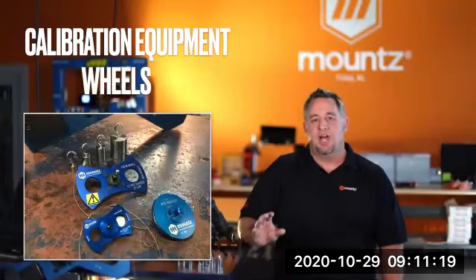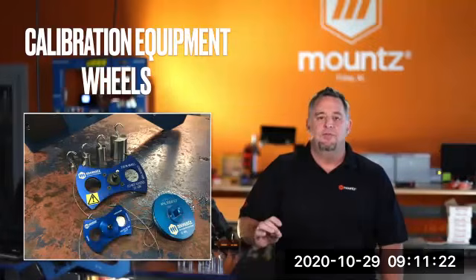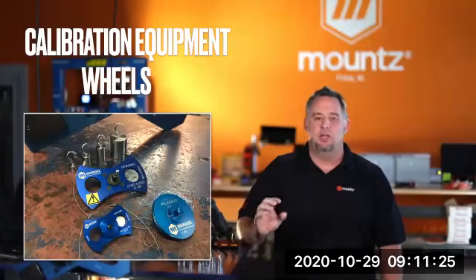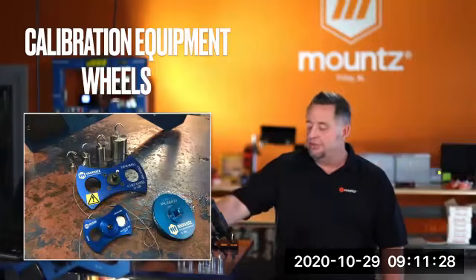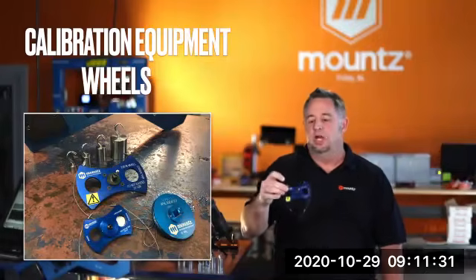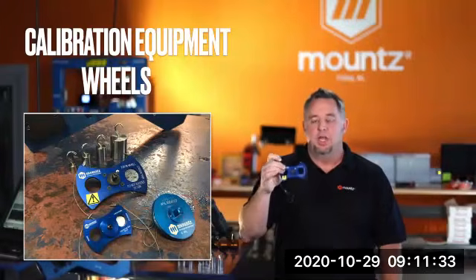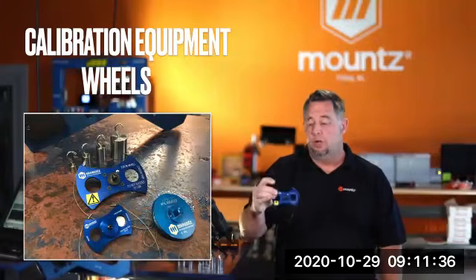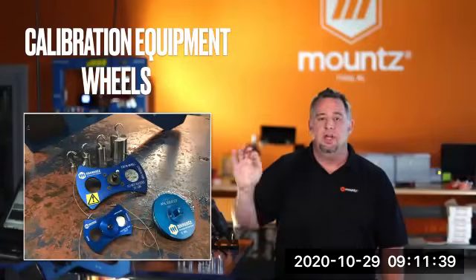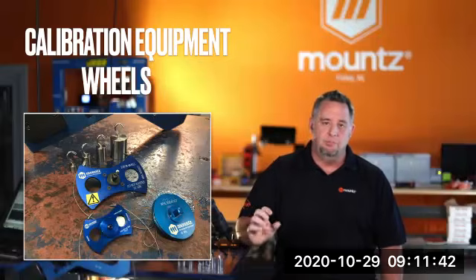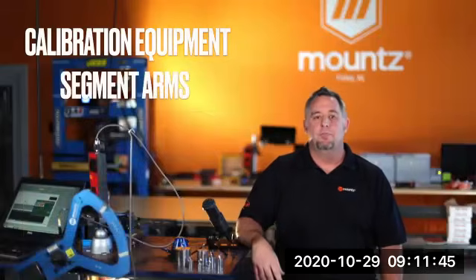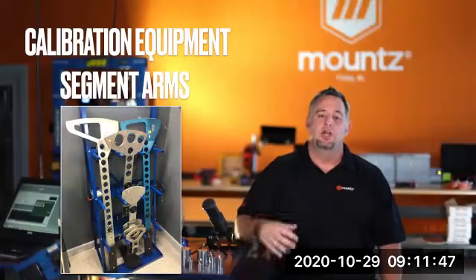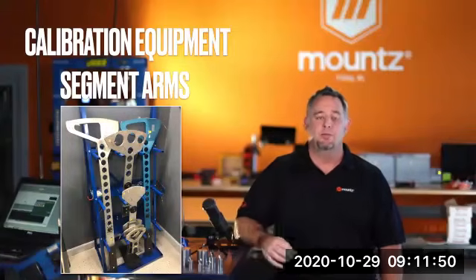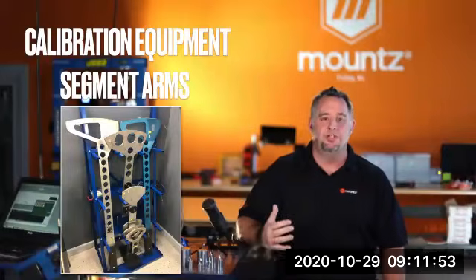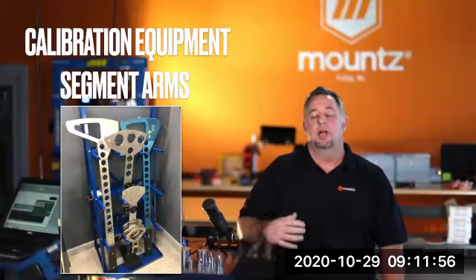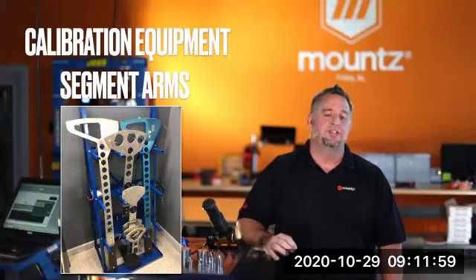So for the different items that we use for the calibration process, for very low torque analyzers and sensors, we use calibration wheels. These allow us to give a known weight at a very low value, for the different low-end torque values. For the larger units, larger transducers, we would use segment arms. These segment arms range from 10 inches up to 48 inches, allowing us to test at different known weights.